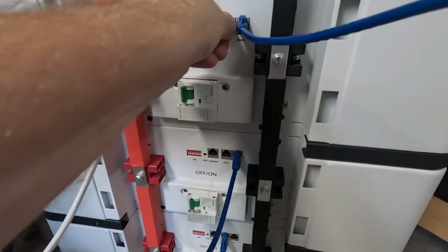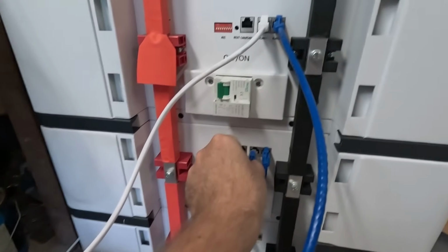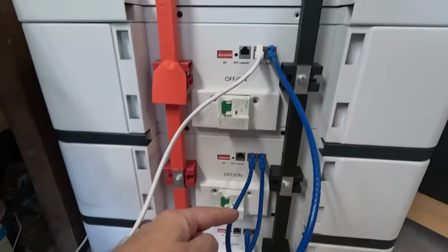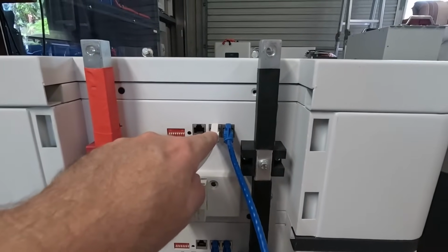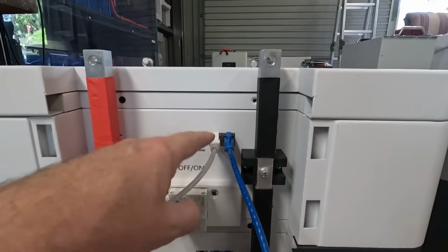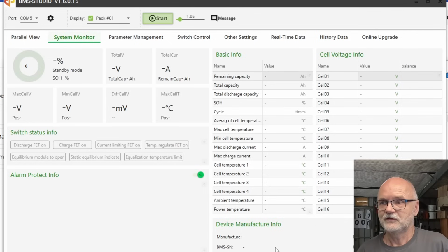You have to fully isolate the battery from a communication perspective. We'll leave this in here for the moment. So while the communication is established, you can only use the RS485 port number 1 on the master battery to communicate to your computer. Right now you cannot change any parameters anymore, and you cannot see any parameters anymore, nothing.